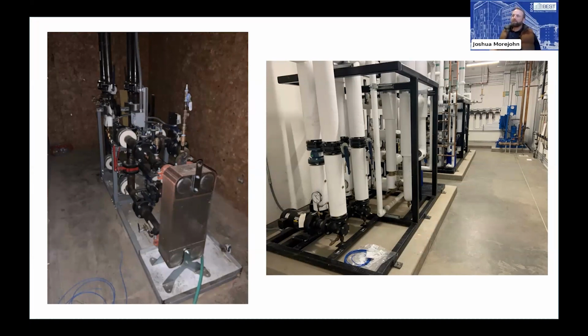In many cases now we're finding we don't even need a heat exchanger — we can just tie directly into the building system and supply the water directly from the loop to the building. We did use heat exchangers in this case; this is showing a brazed plate heat exchanger, typical of what we put in the buildings, mostly because we were concerned about old building systems with closed loops that hadn't seen any outside water source for a long time, and what opening them up to the loop could do, and the complications there. But we haven't had many problems on the buildings where we tied in directly without a heat exchanger, and we're looking to do that more in the future to save costs and equipment maintenance.